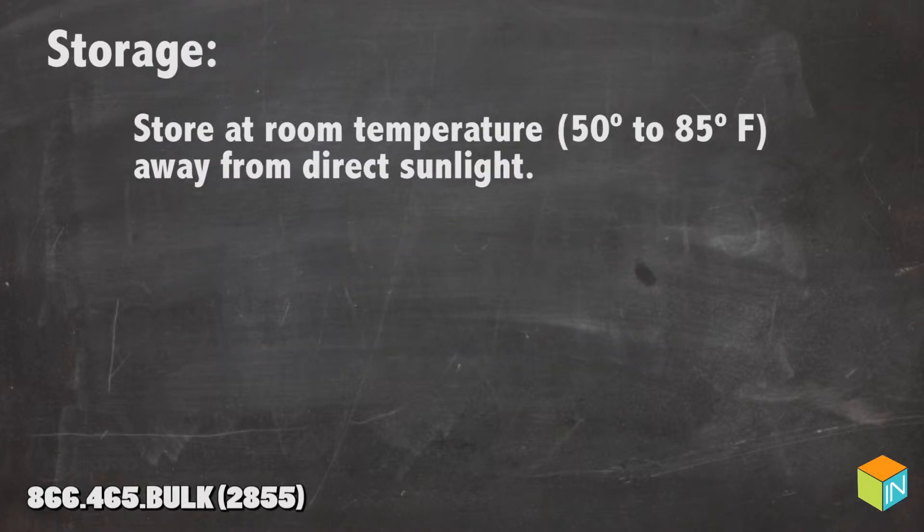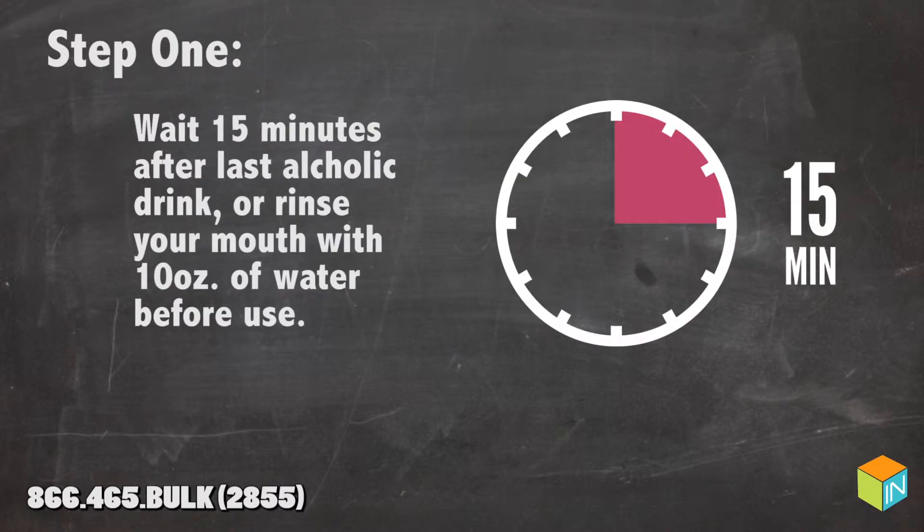When storing the AlcoCheck Breath Alcohol Screen, you should always leave it at room temperature, about 50 to 85 degrees Fahrenheit, away from direct sunlight.